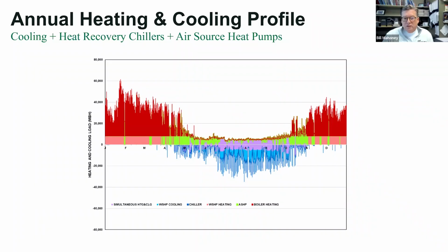So coefficient of performance, and to put numbers on it, it's a ratio of how much energy you put in. These are all compressorized. How much electric energy I put into the compressor versus how much useful heat energy I get out in a heating COP, or how much useful cooling I get out in an air conditioner, a chiller or something like that. And then, for instance, the purple, I'm putting a kW into the compressor, and I'm getting out useful heat and useful cooling, and therefore the COP gets up to like the 6 and 7 range for that. Some of these other ones, the salmon heating from the ground, that's 3. And so that's what you get. That's kW out versus kW in.